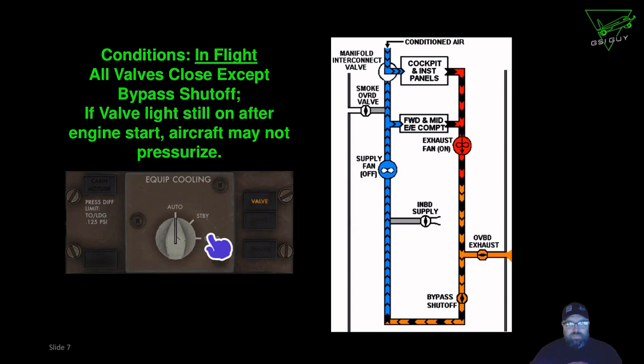Now, in this case, when we look here, the overboard exhaust has stayed open. Now up here, I've made a mistake. I put all valves closed except for the bypass shutoff valve. That's not true. In this case, it's the overboard exhaust that didn't close. So that's my mistake. I'm going to go back and fix it. But for the purposes of this video, it's the overboard exhaust that's open. And that's pretty self-explanatory looking at the picture, right? Now, the valve light's going to come on. And if you remember what we've said with all these other systems, a valve light is either in transit or a disagree. Well, in this case, it's a disagree because it should be closed and it's open. So that's why the valve light's going to be on.